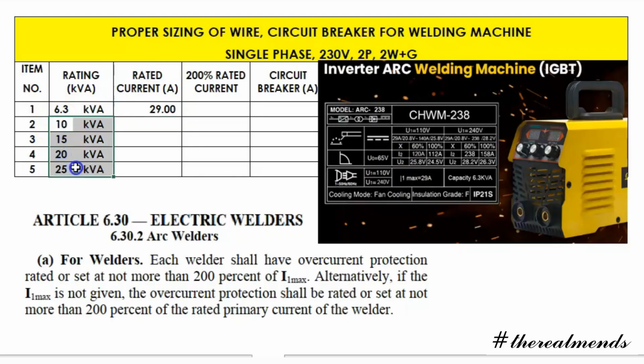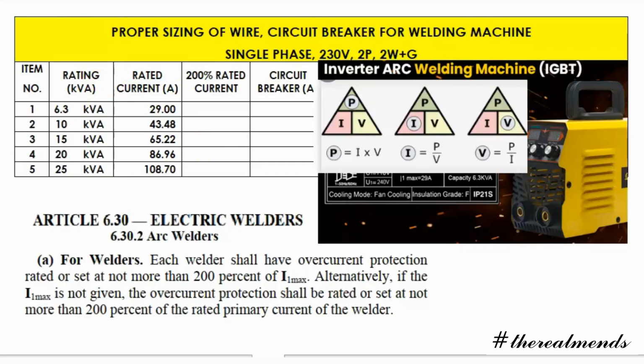So for the successive welding machine, wala tayong nameplate, but it says rated not more than 200% of the rated primary current. So if wala tayong nameplate, meron tayong alternate formula na gamitin to solve for the rated current, which is by using this one. Ito yung power triangle. So to get the current, just divide the power over the voltage. So from that, itong 10 kVA or known as 10,000 VA, let's divide that by 230 volts. So after that, maka-arrive tayo na 43.48 amperes. So if itarag natin to, we have an answer to.